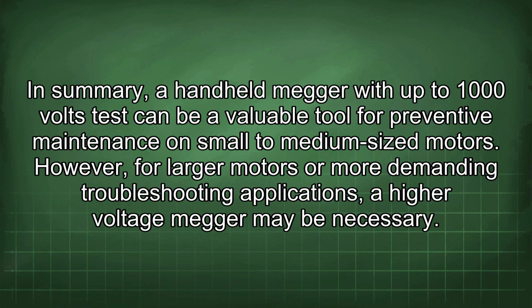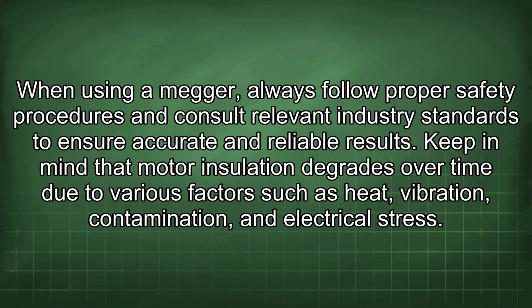In summary, a handheld Megger with up to 1000 volts test can be a valuable tool for preventive maintenance on small to medium-sized motors. However, for larger motors or more demanding troubleshooting applications, a higher voltage Megger may be necessary. When using a Megger, always follow proper safety procedures and consult relevant industry standards to ensure accurate and reliable results.